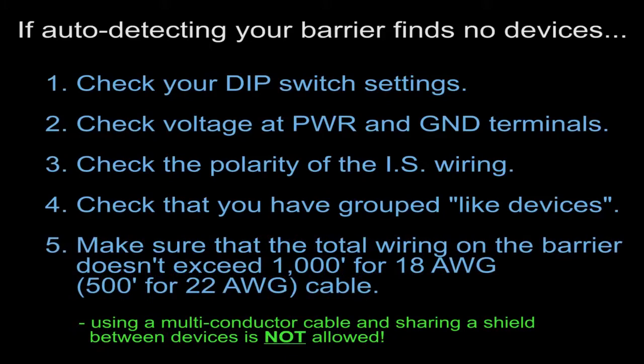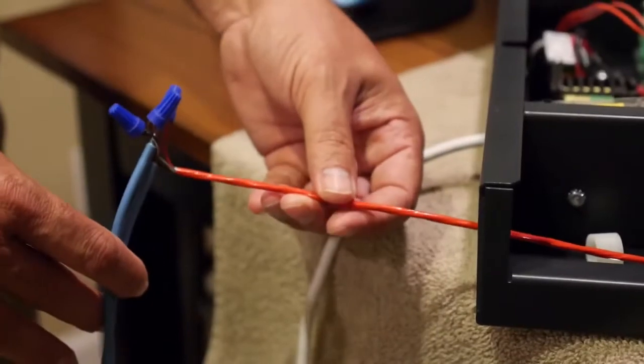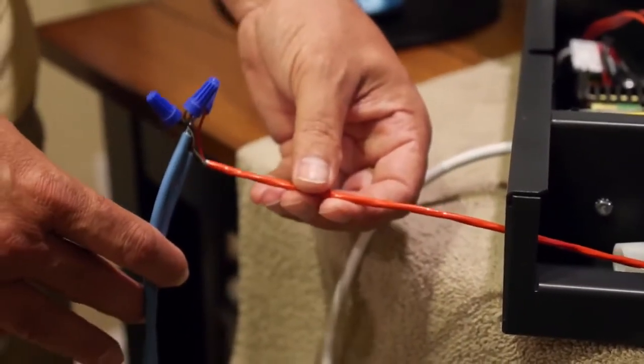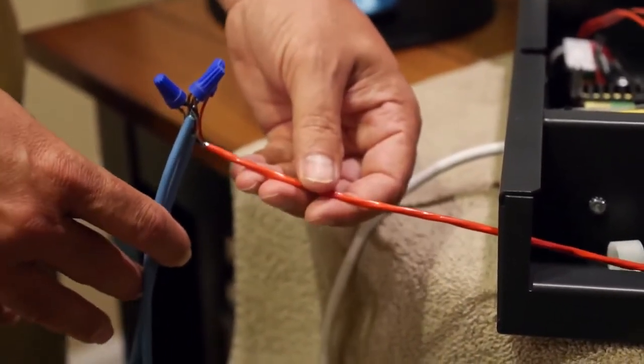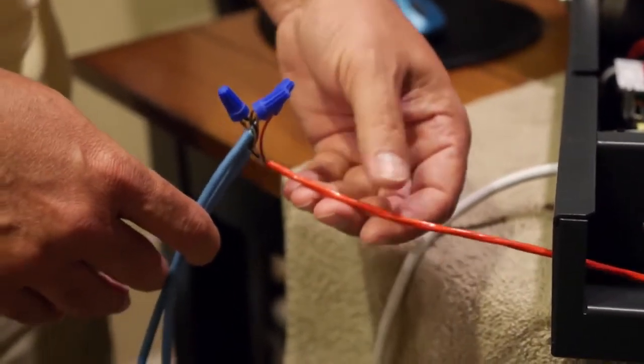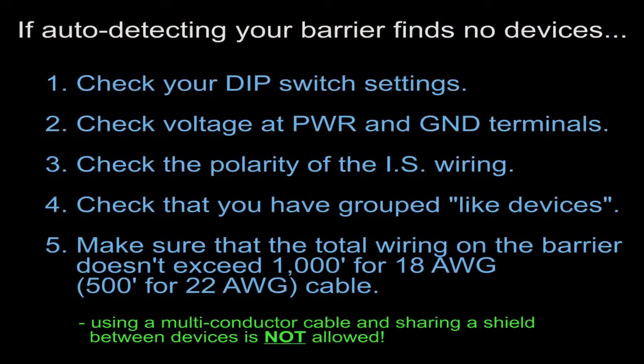You need to make sure that the cable that you're using, the 8760, is good for 1,000 feet. And the 8761, which is the 22 gauge version of the same cable, is good for 500 feet. The one thing that you have to remember is that it's total length of wire. So if you do have home runs coming back to the building, make sure that your total wire does not exceed 1,000 feet if it's 8760, or 500 feet for 8761.